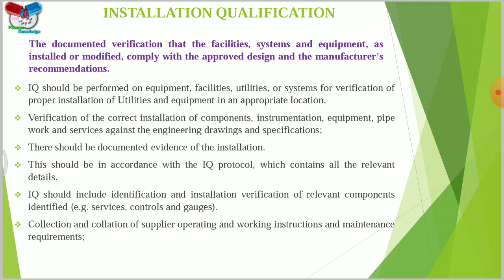So any deviation and non-conformance, including those from URS and acceptance criteria specified and observed during installation qualification, should be recorded, investigated, and corrected or justified. The outcome of the IQ should be recorded in conclusion of the report before OQ is started.